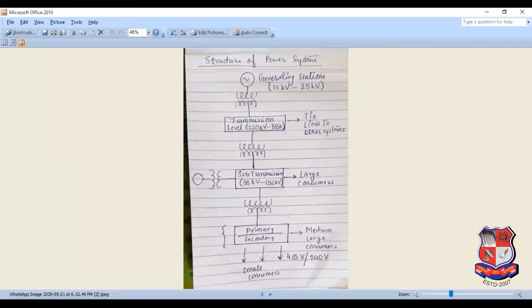Now the question arises in your mind, why are we generating power at low voltages? Because as we increase the voltage, the insulation requirement of the generator will increase, so the size of the generator will increase, and this will lead to higher cost of the generator, the space, and the maintenance. So there are many things. For that reason we are generating power at low voltages, right? So we are generating from 11 kV to 25 kV, in between this. Then it depends upon the power station, which type of fuel you're using, and which type of station it is, okay.